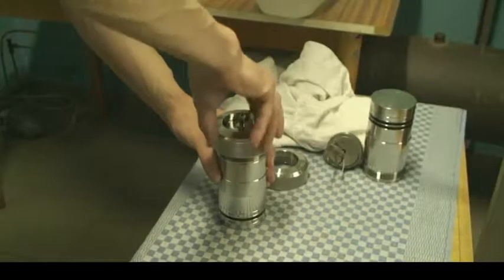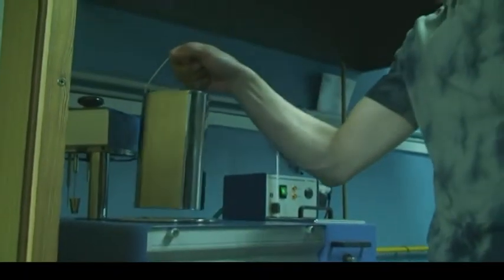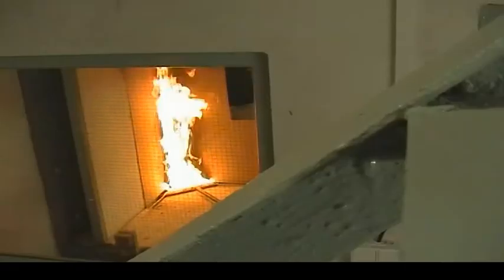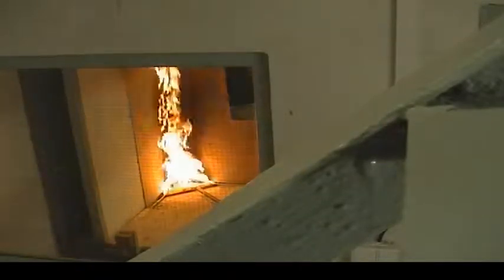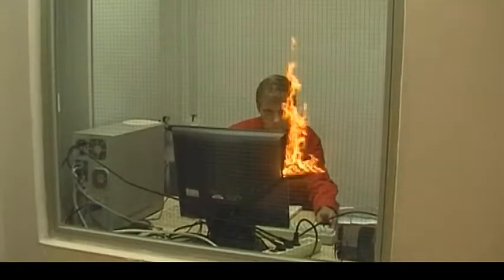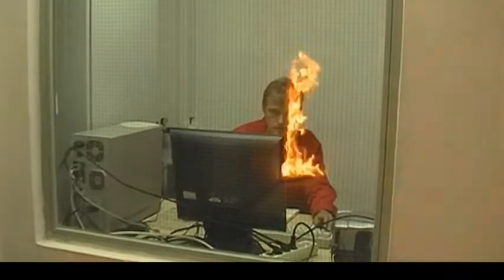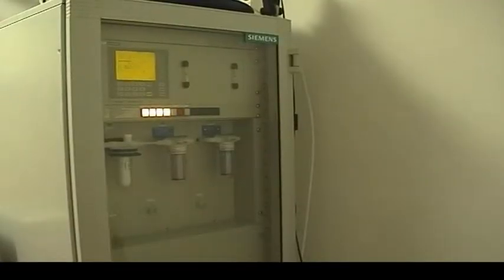Determination of combustion heat, according to EN ISO 1716. The most demanding reaction to fire method and the most complicated equipment is the one for testing the products exposed to heat influence of a single burning item, the so-called SBI test, according to EN 13823. That equipment was supplied to PAVOS and installed by a foreign manufacturer. Identical testing equipment, including validated software, has been used by roughly 50% of European testing laboratories.